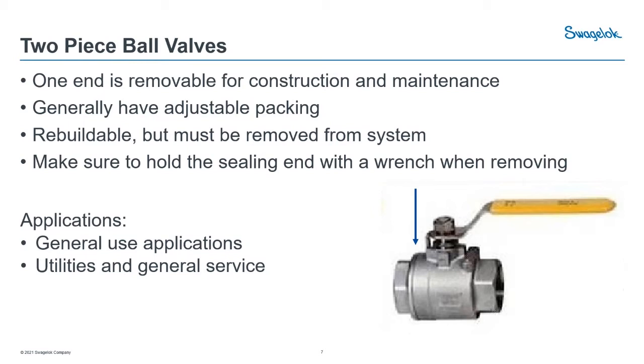A pro tip: make sure you hold the sealing end with a wrench when removing it. Where that seam is, there are nut flats on the seal piece. If you're loosening a threaded NPT pipe with a pipe wrench, always put a wrench across those nut flats — because as you're trying to loosen the nipple, you can accidentally loosen the body end, which immediately relieves tension on the seat. If you have any pressure on the other side, you can have a leak immediately, which is very dangerous. Ideally, don't take these apart when under pressure.